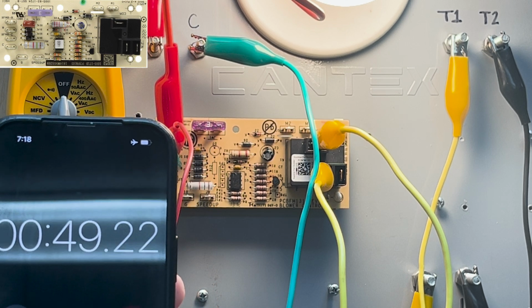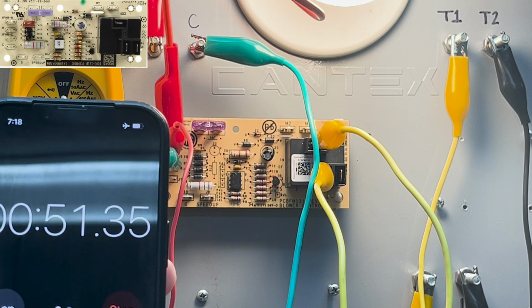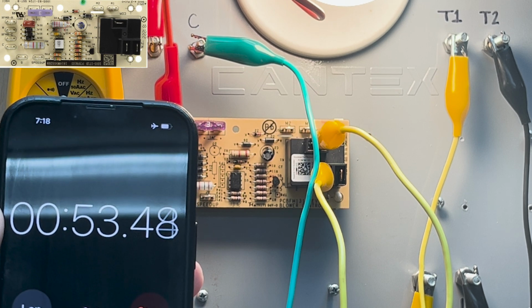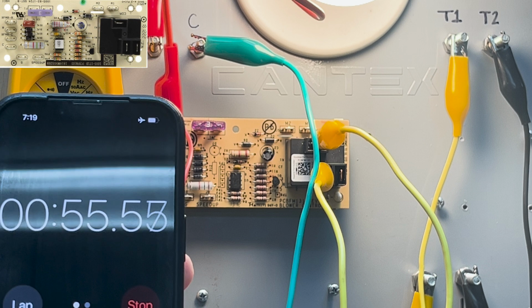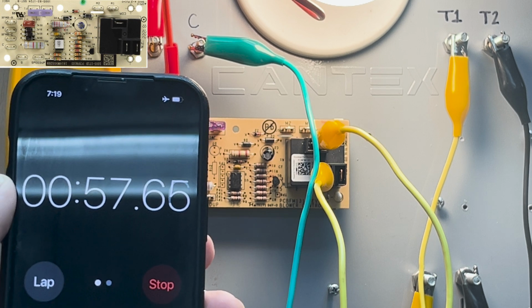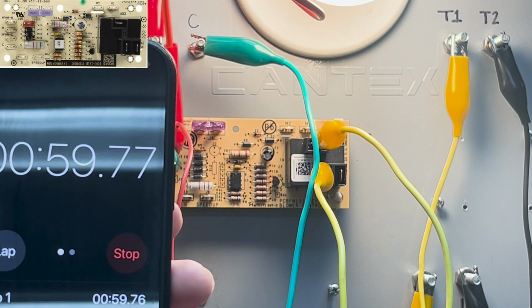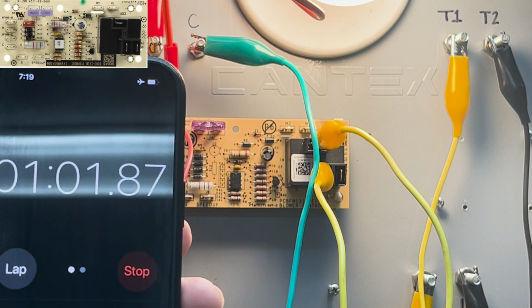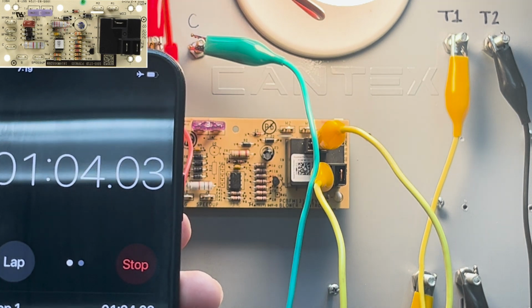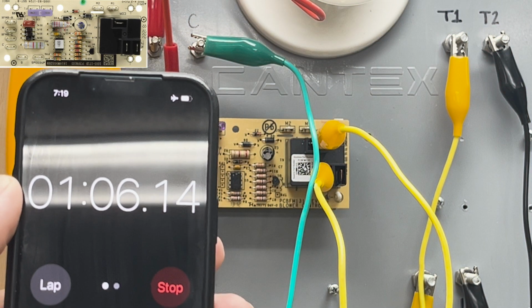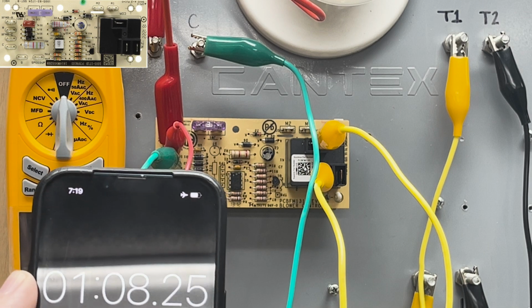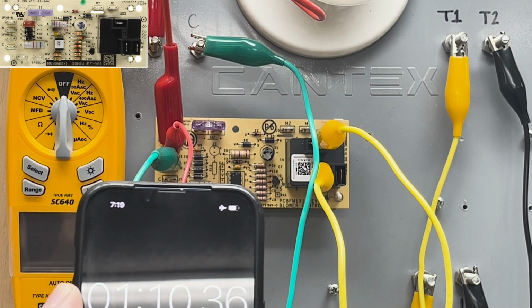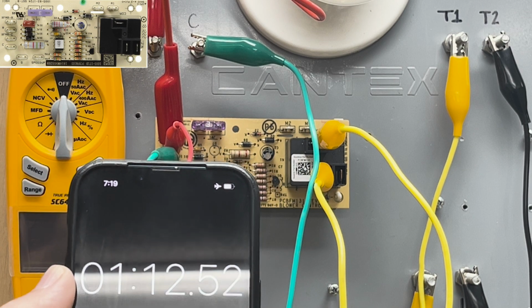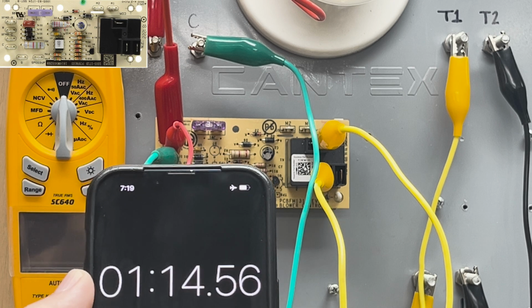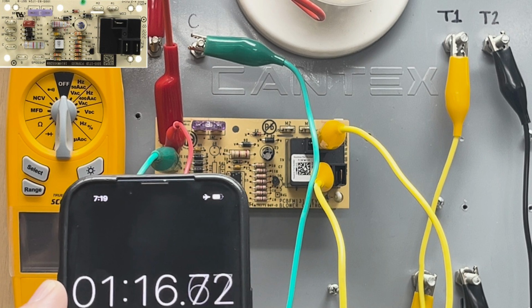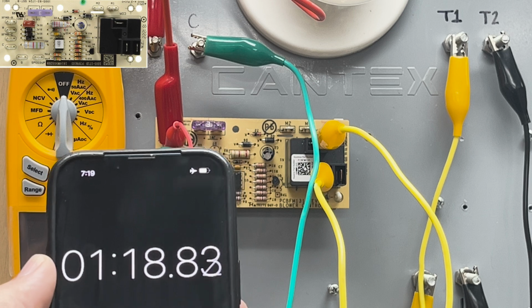Get you a new PCB board. There is another board very similar to it, called the ICM 277. It looks identical, and International Comfort, ICM, those products are very similar. You might have a 5-amp fuse on those. Don't be worried if you put a 5-amp fuse in there. I know Goodman's going to recommend a 3-amp fuse. If you have a 3-amp, put a 3-amp in there. If you have a 5, it's not going to hurt anything.